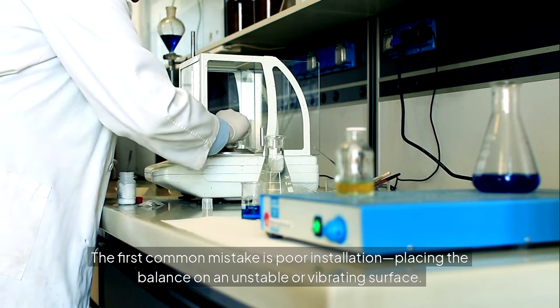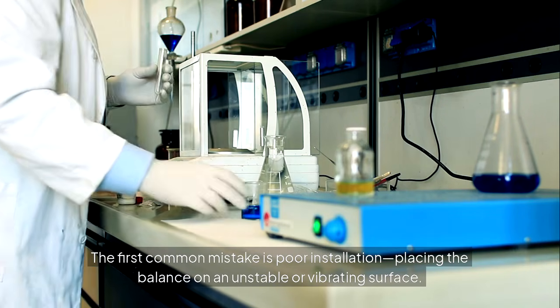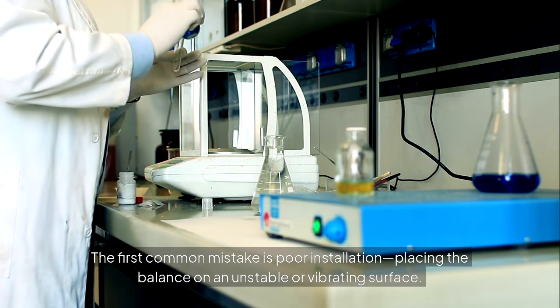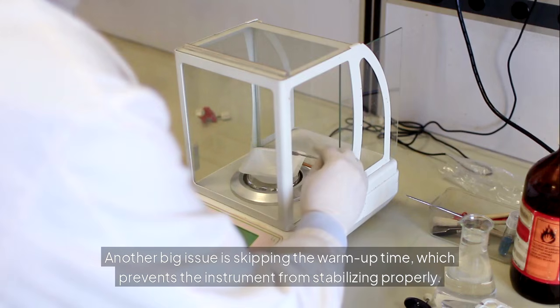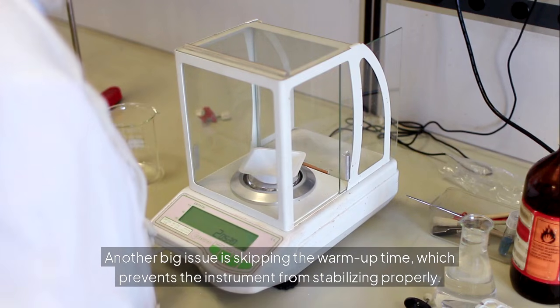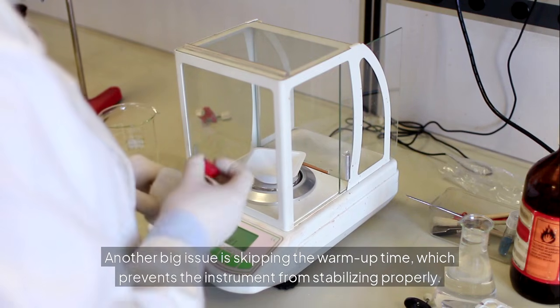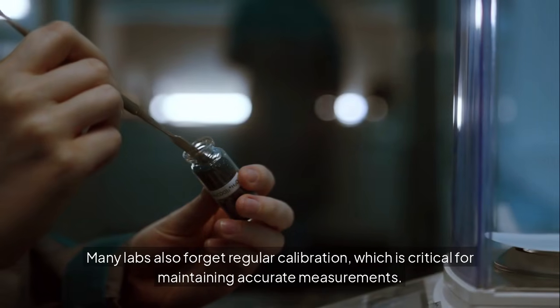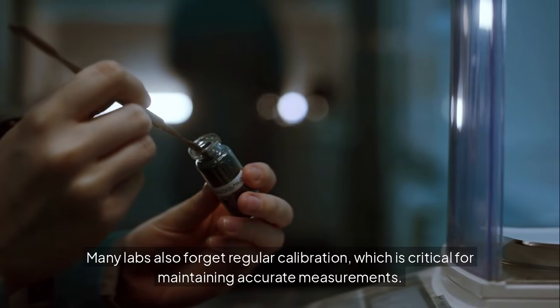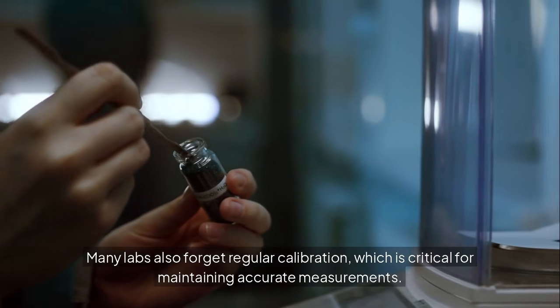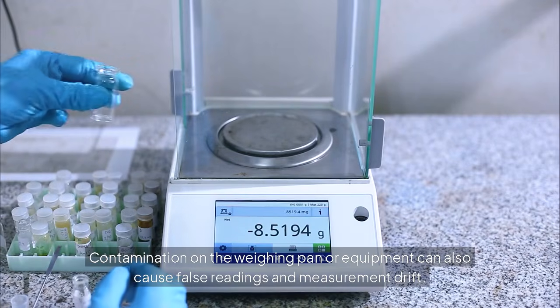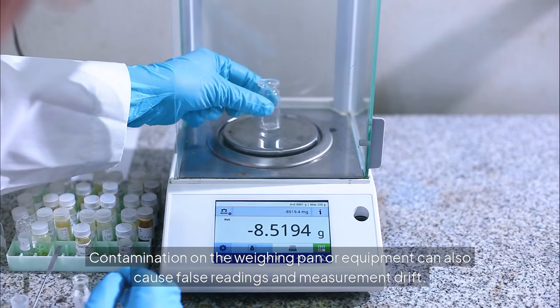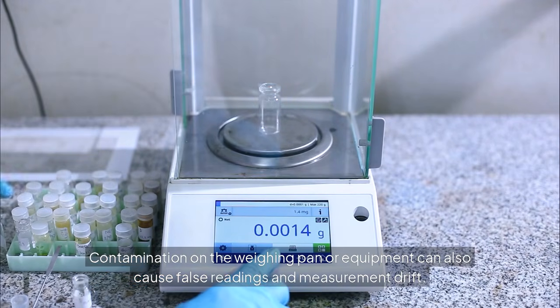The first common mistake is poor installation, placing the balance on an unstable or vibrating surface. Another big issue is skipping the warm-up time, which prevents the instrument from stabilizing properly. Many labs also forget regular calibration, which is critical for maintaining accurate measurements. Contamination on the weighing pan or equipment can also cause false readings and measurement drift.